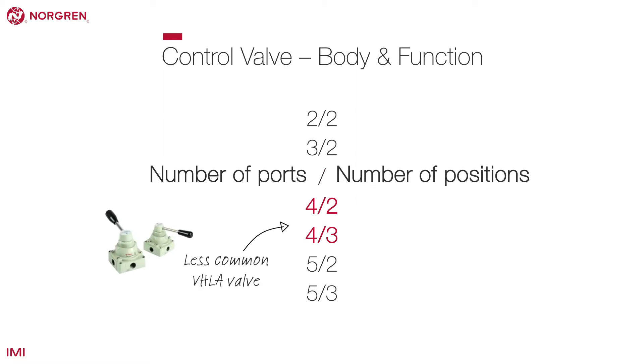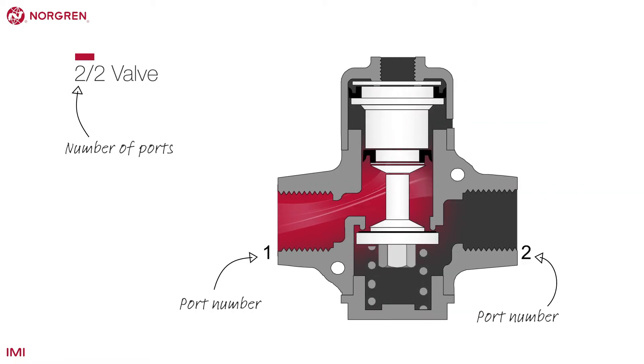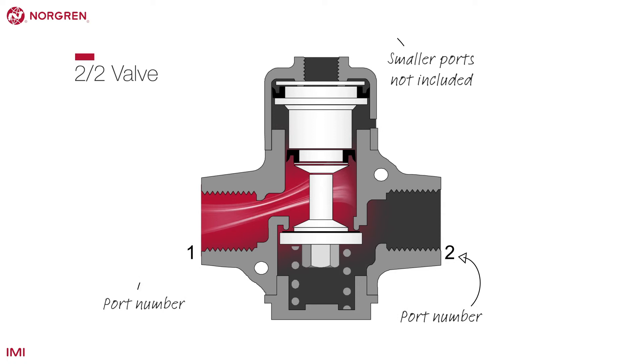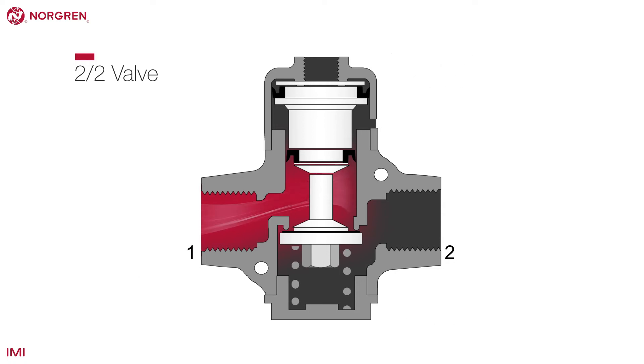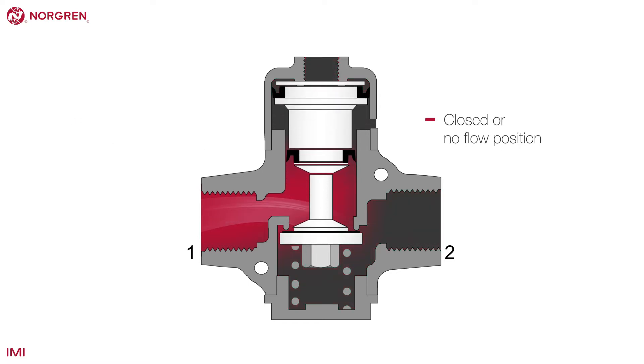They are commonly displayed like this. The first number represents the number of ports on a valve. Only the ports on the main body are counted; the smaller ports on a pilot valve, for example, are not included. This is a 2-2 valve — it has two ports and two positions. Port 1 is the inlet or supply, port 2 is the outlet or output. This is a standardised numbering system. The operation of the valve is also indicated by a number — in this case it's 1-2, which refers to the flow of air from port 1 to port 2.